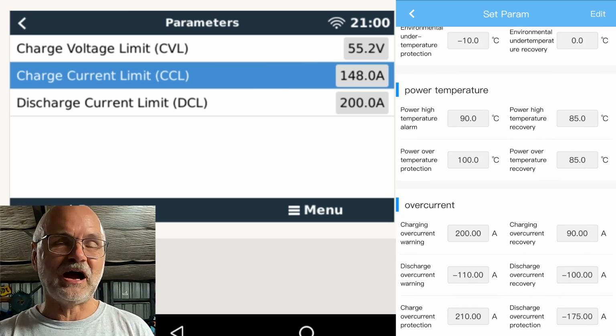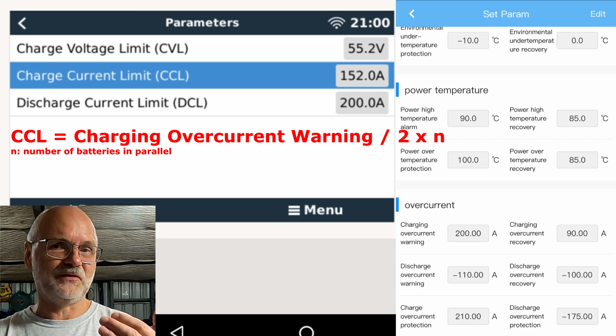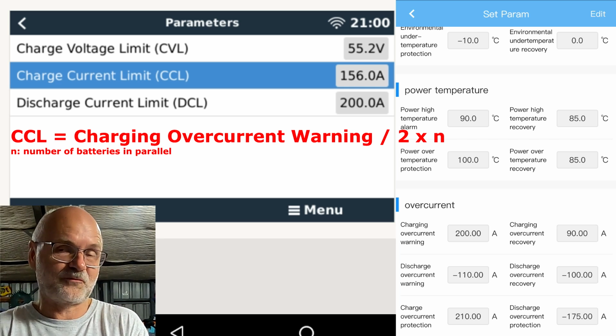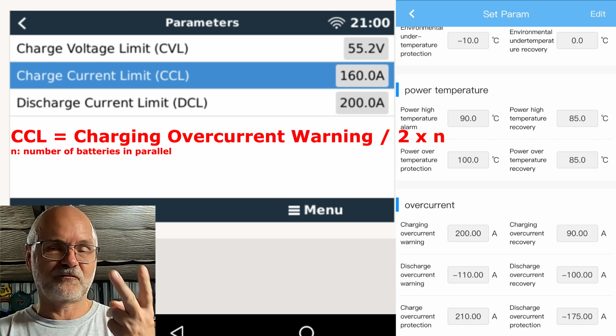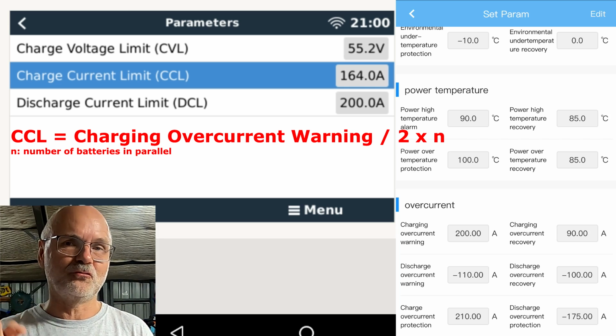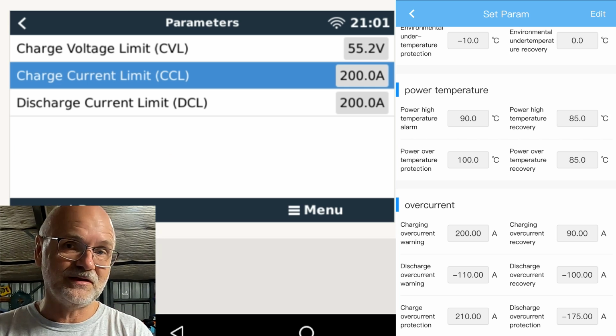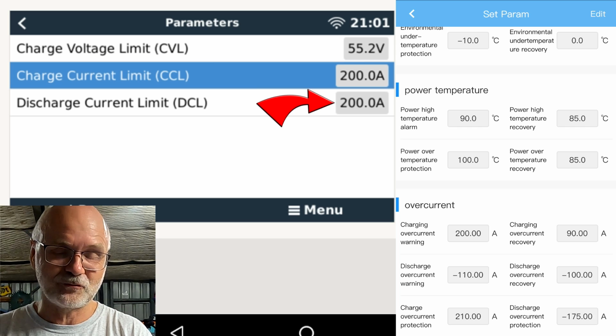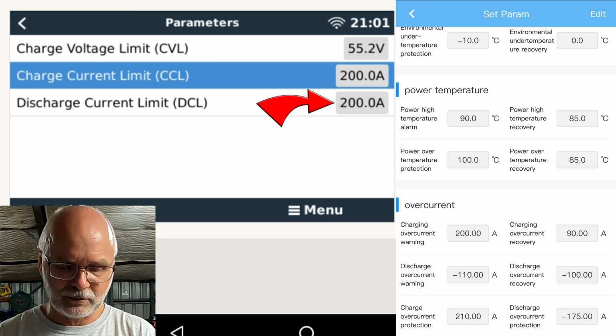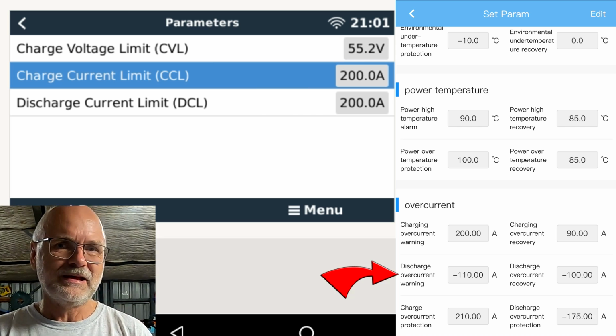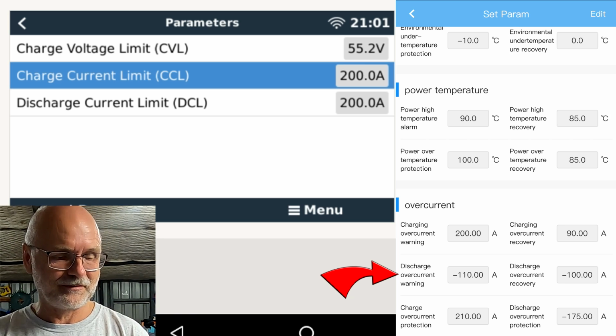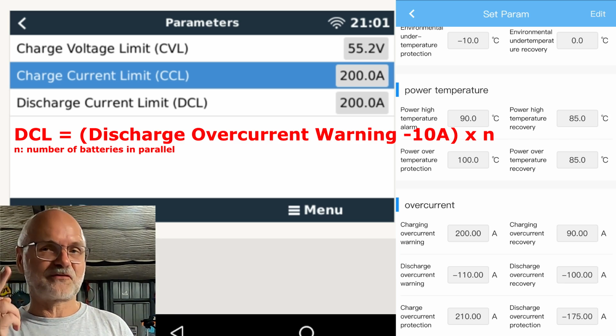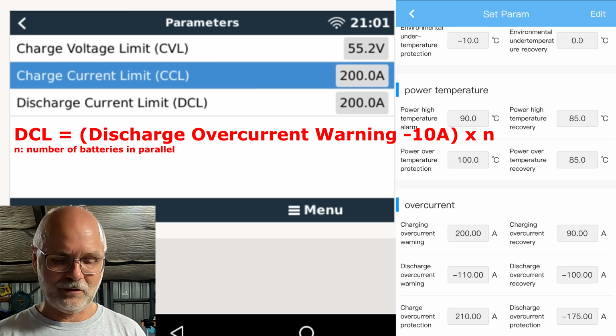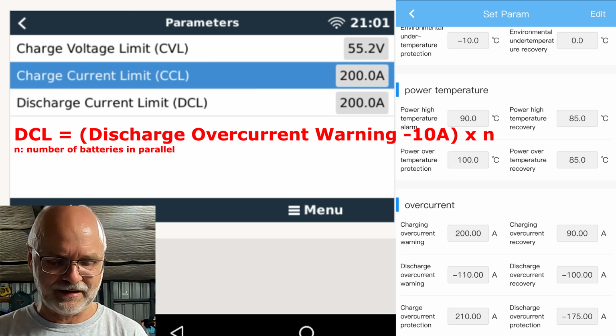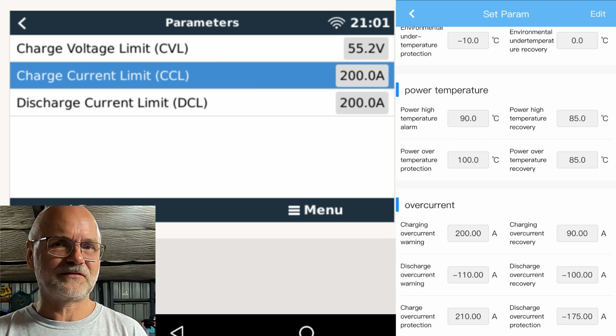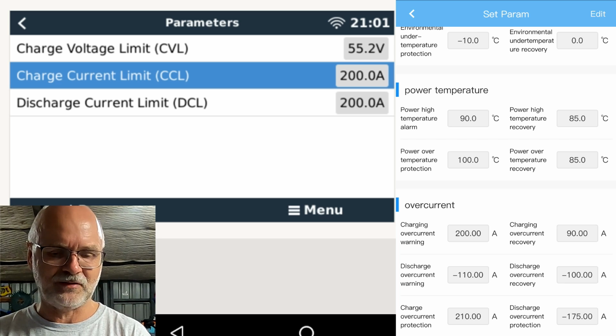So here it is, charging overcurrent warning divided by 2. That's what it was for one BMS. And now we've got 2 BMSs, so it's times 2 again. And as you could see, the discharge current limit increased as well. And this was our discharge overcurrent warning, minus 10 amps. And again here it is then times 2, because we've got 2 batteries in parallel now.